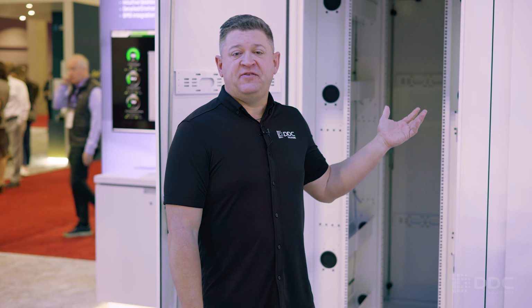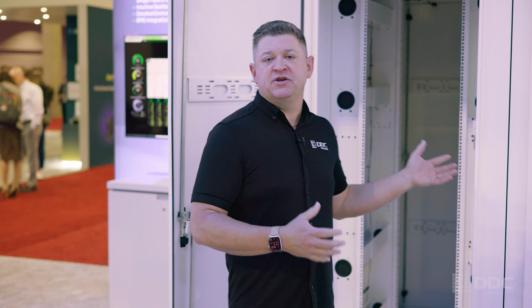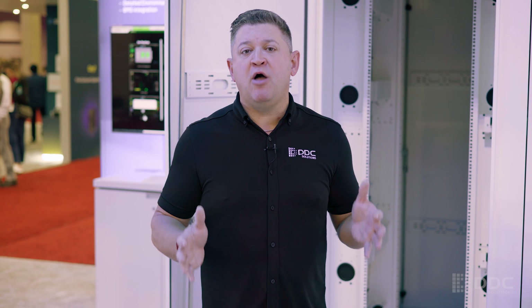From the front of the cabinet, you'll see a variety of different changes. While DDC is currently the highest density air-cooled solution, we've made modifications to the cabinet itself to support a variety of different liquid-to-chip and liquid-to-chassis solutions. With 100 kilowatts of pure air-cooled capability, many data center operators will find they have a very long runway before they have to decide which workloads they're going to bring liquid-to-chip to.